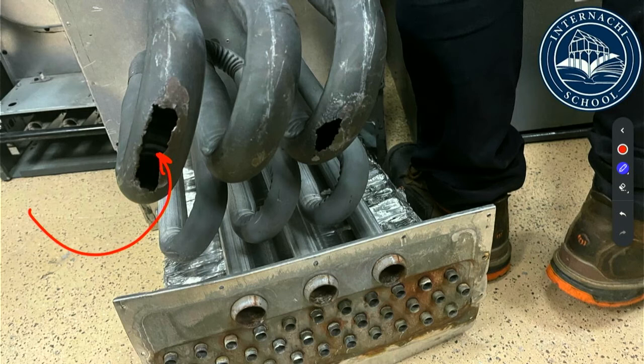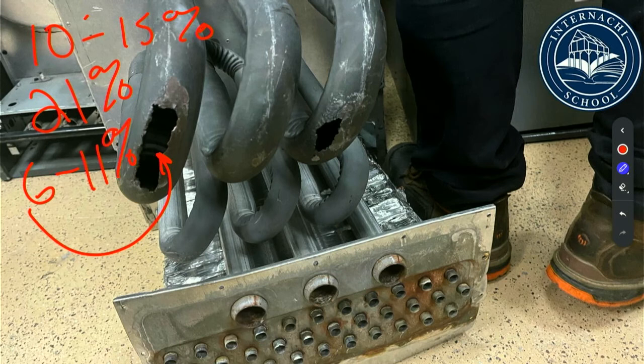When we know that oxygen is needed to make a fire, we know that oxygen is going to be using anywhere from 10 to 15%. We know there's roughly 21 percent of air that's there. That means I should be between 6, and I usually kick it up to 11. I should be between 6 and 11% of oxygen after the fire. Now if I have more air blowing in here, I'm going to have a higher number of oxygen. So when I get to 12 or more, then I know I'm getting fresh air added into this thing, and then it's bad.